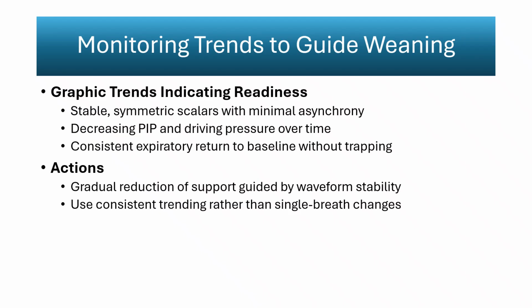Weaning is performed incrementally, guided by sustained waveform stability. Each reduction in PIP, VT target, or support pressure should be evaluated over multiple minutes to ensure preserved symmetry and no emergence of scooping, missed triggers, or rising baseline flow. Using trends prevents premature changes driven by transient motion, artifact, or spontaneous breaths that do not reflect true readiness. When trended correctly, the graphics provide continuous feedback on the infant's physiologic tolerance to weaning and help prevent setbacks from undersupport or early fatigue.